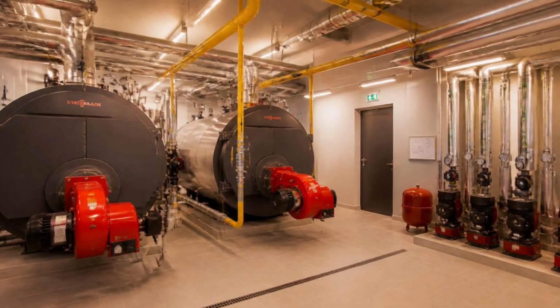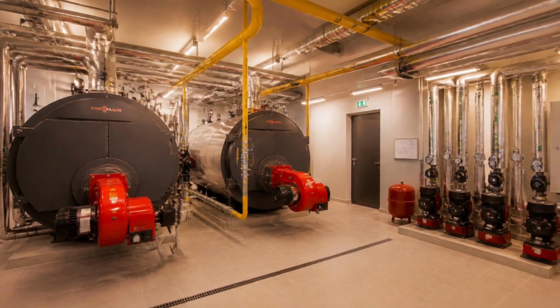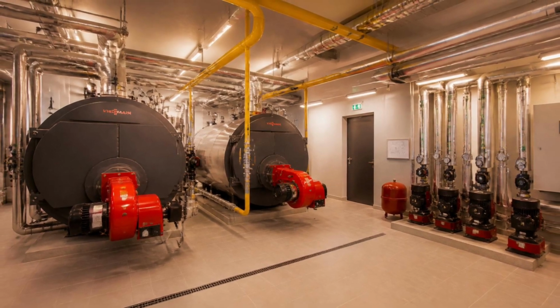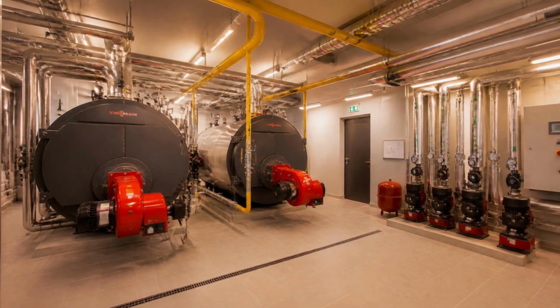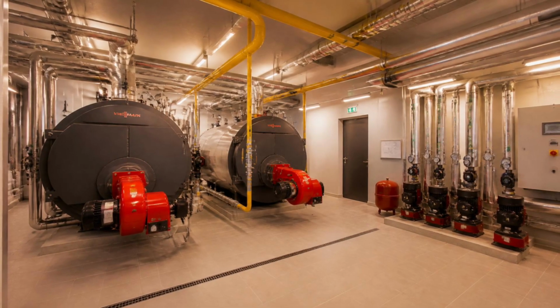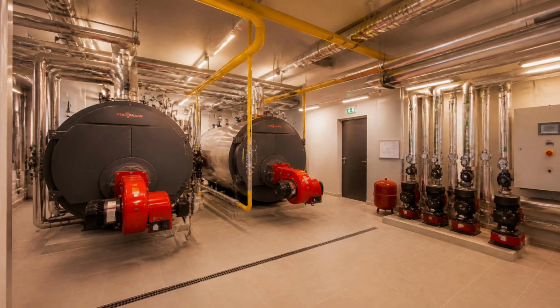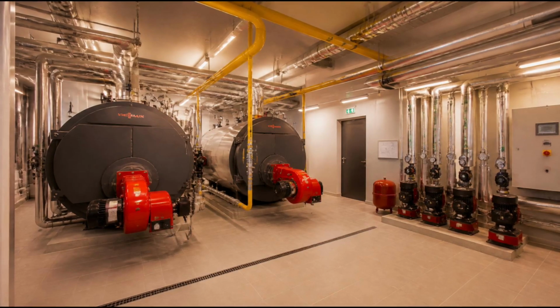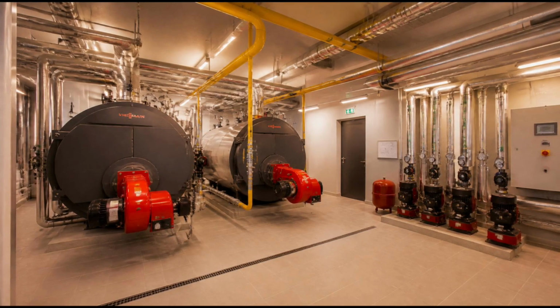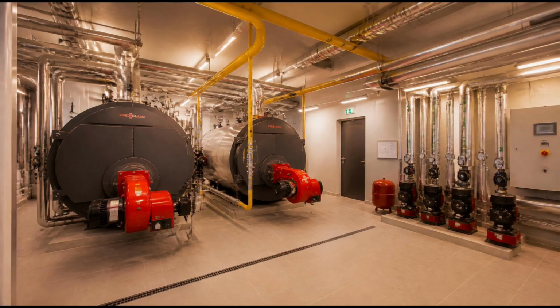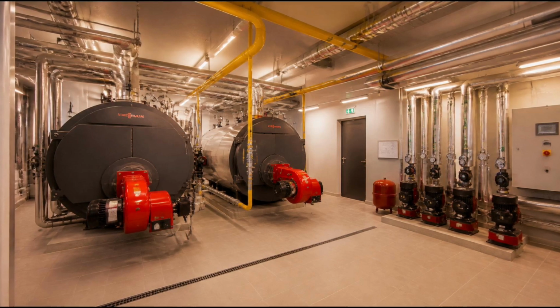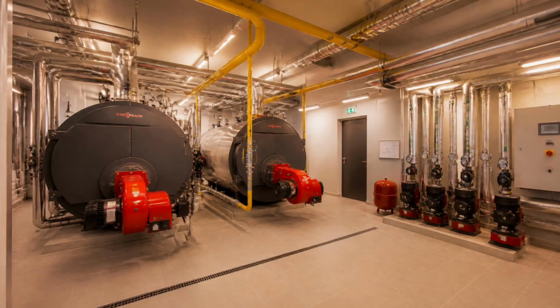Throughout the building, sensors measure temperature, humidity, airflow, carbon dioxide levels, and occupancy. Each of these measurements is collected and sent back to the building automation system, which compares the current conditions to the set points that have been programmed into it. If a room is too warm, the system directs its VAV box to open wider. If a zone is unoccupied, it may reduce airflow to that area. If outdoor conditions change, it adjusts the ratio of fresh air to return air accordingly.